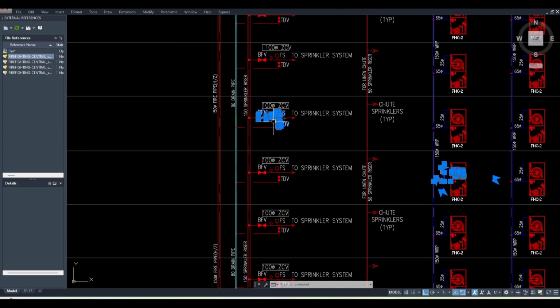Same way with sprinklers. The minimum distance to the wall cannot be less than 100 mm. It cannot be 1.8 meters away from there. The distance between two sprinklers cannot be less than 1.8 and cannot be more than 4.5, right? So all these things you can see visually. If it looks a little bit weird, you can check it and verify whether the system is done correctly or not. Now, say they have installed 700 sprinklers in a line, and you get them all with only one zone control valve. They are covering more than 4831 square meters of area. That is wrong code-wise, so you can correct that also.